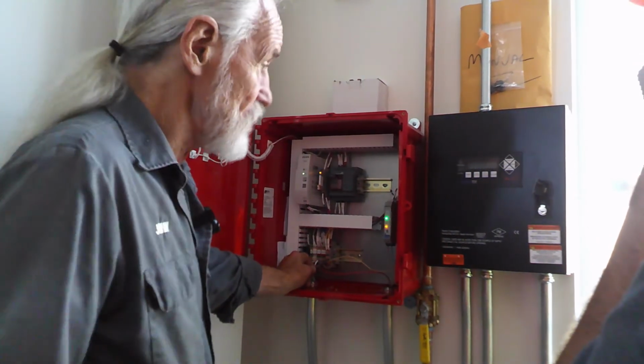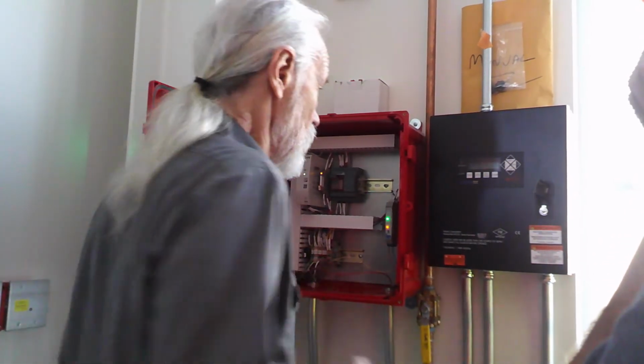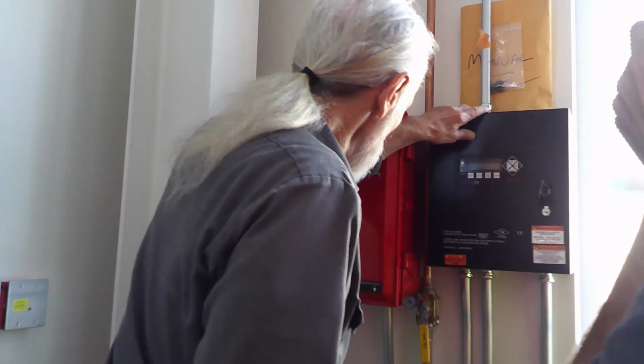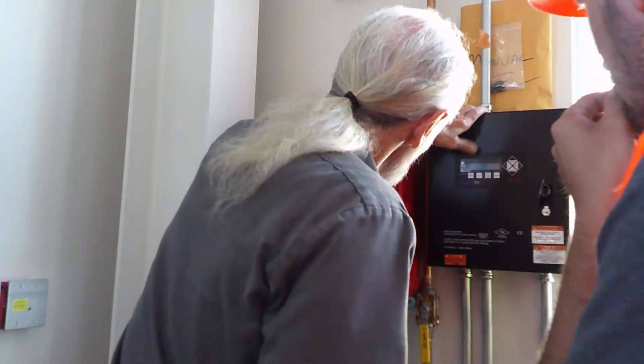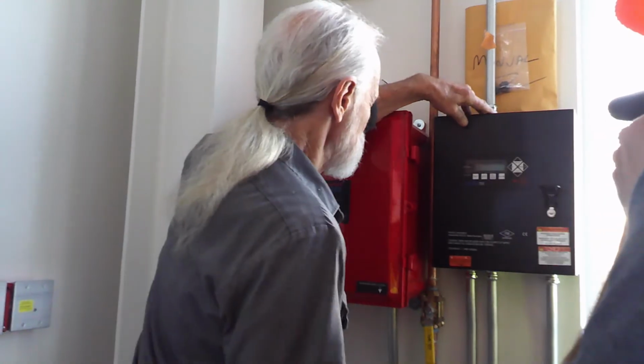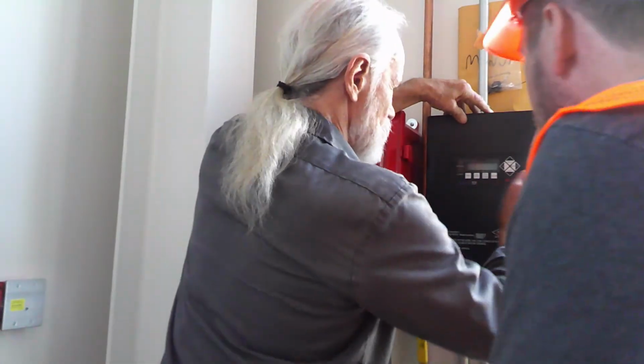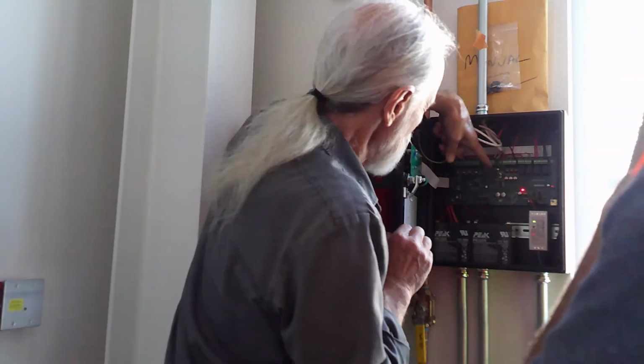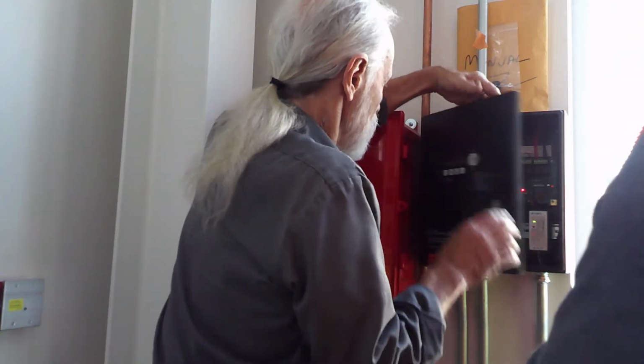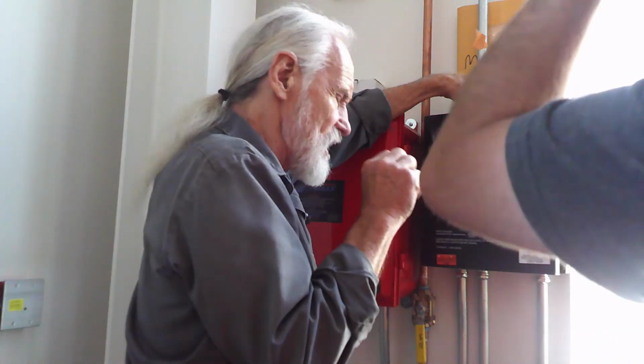This should shut the unit down, but it's blocked. Okay, so check if this thing is lit. Yeah, you can't really read it. This says service mode, okay? Now when you're fooling with it, see that toggle? You should put it into service because that allows you to check each component individually.